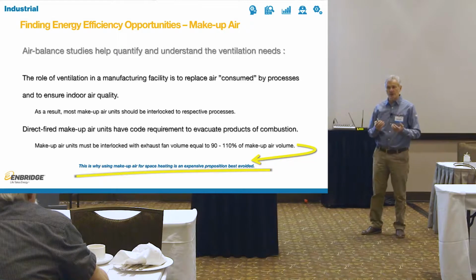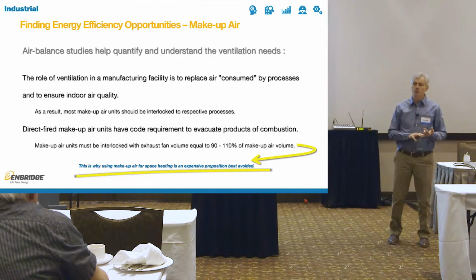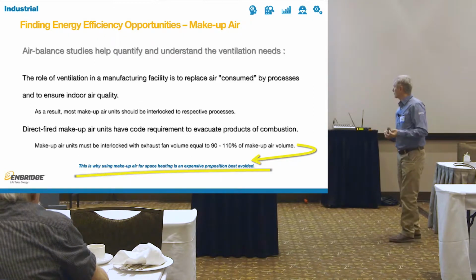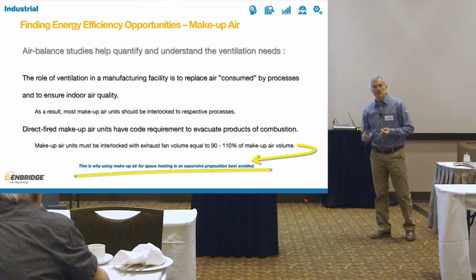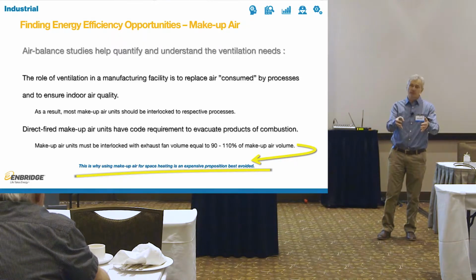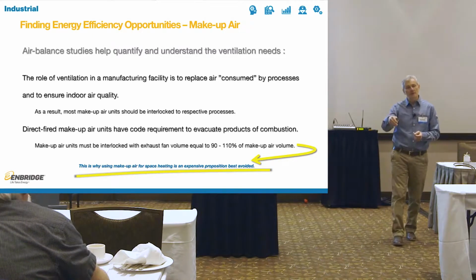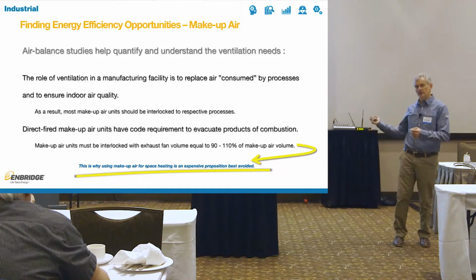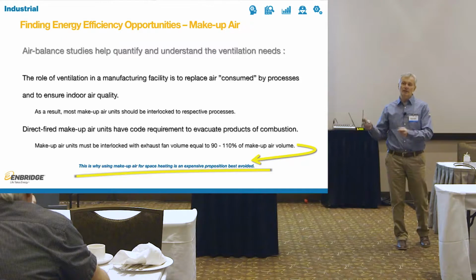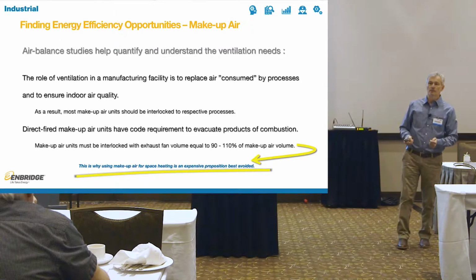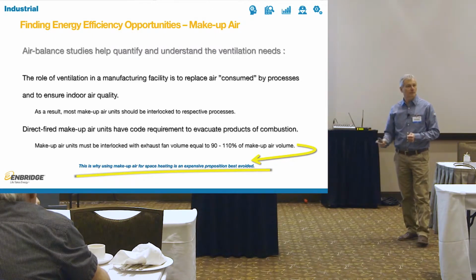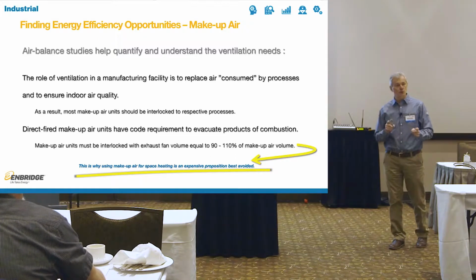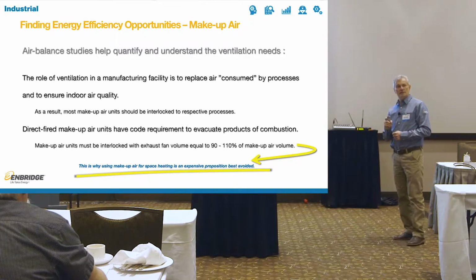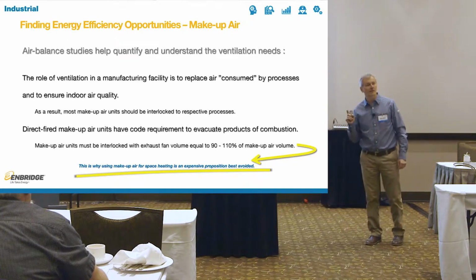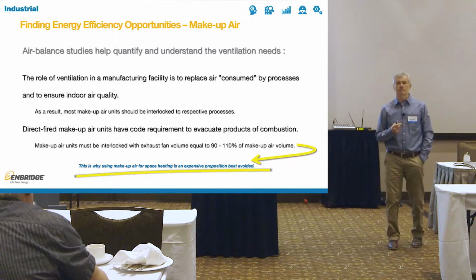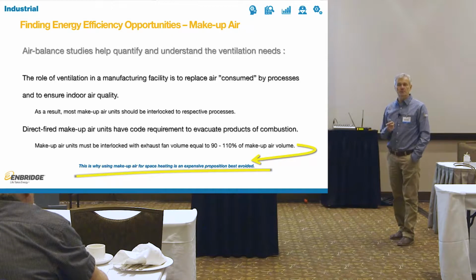Direct fired makeup air units are very common in industrial facilities, the most efficient way to provide makeup air if you have to provide some. So it's very popular. For them, you have to also provide some exhaust because they put products of combustion in the place. So if you have 100,000 CFM makeup air units that are direct fired, you have to have, by TSSA rules, 100,000 CFM thereabouts interlocked to that makeup air. Again, most of you will not have it interlocked because you're grandfathered from God knows when and it just keeps going on. So it will not actually be interlocked. It should be, but it's not. And I know that many of you are questioning that, but you can go and turn off your makeup air and see how many exhausts turn off at the same time. And it probably won't be many. You would be surprised.